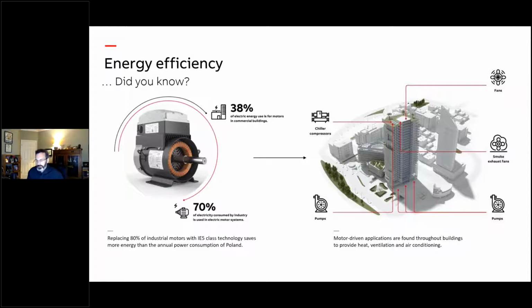So, fundamentally, we're going to be talking about motor technology here today. However, I would tell you that the biggest contributor to system efficiency is the design of the pump or the fan in and of itself. And what I would tell you is, you want to pick a motor product or technology that when you apply it to that pump or that fan is going to give you as much flexibility as you possibly can to innovate on the design of the fan or the pump, because that's really going to get you your highest efficiency level. And so again, that's why this motor technology that we're talking about is built into a standard induction motor frame so that it can kind of drop in where standard premium energy efficient motor is today and provide that flexibility, right?